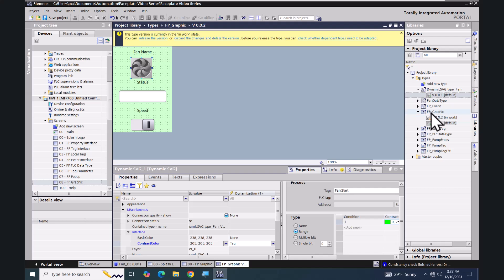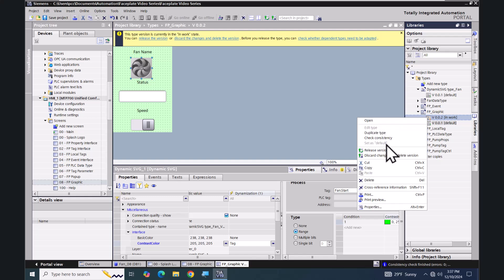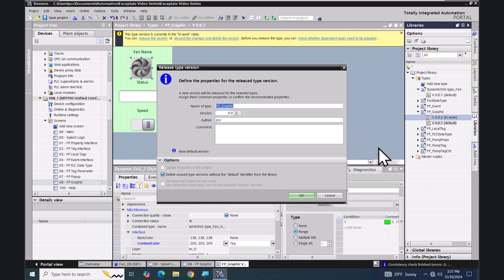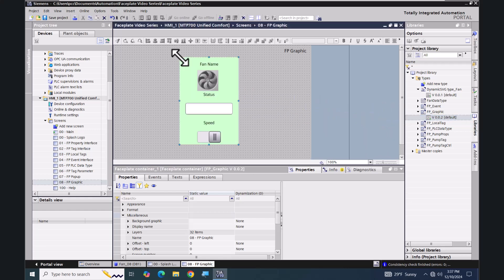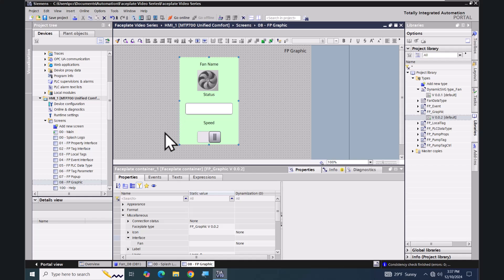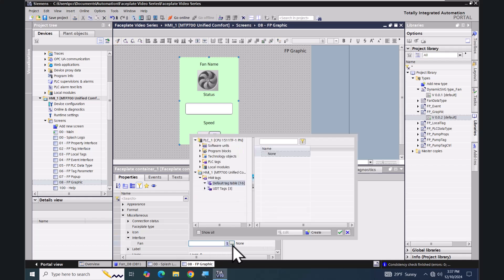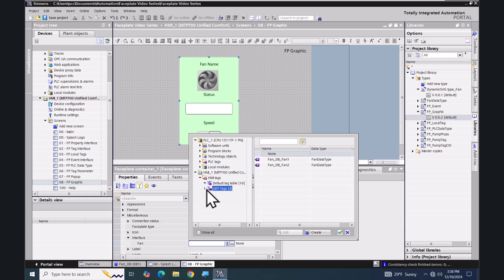The FP graphic is still in work, so I'm going to right click on it and select release version. I will keep delete unused type versions checked and say OK. I will bring in an instance of our FP graphic, go down to the miscellaneous area in the interface, and assign it to fan underscore db underscore fan one, which is of the fan data type.